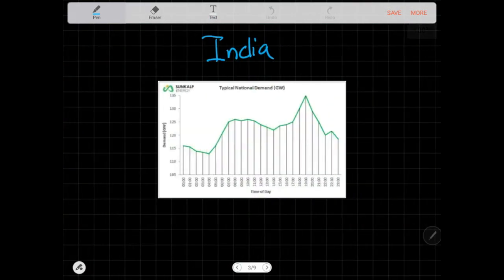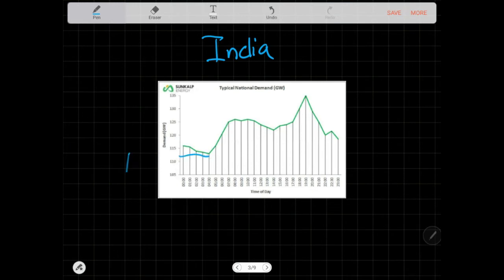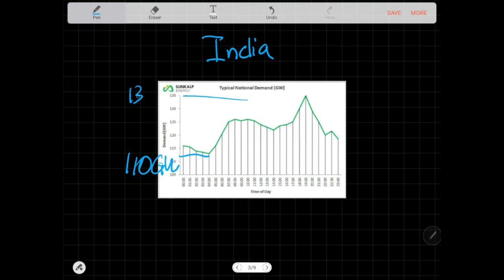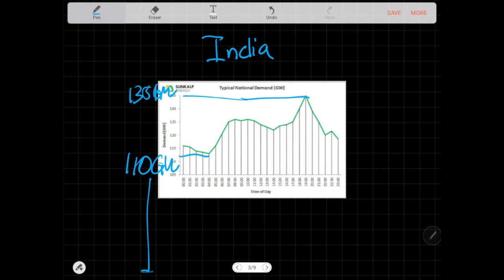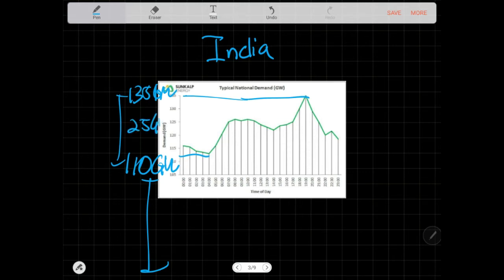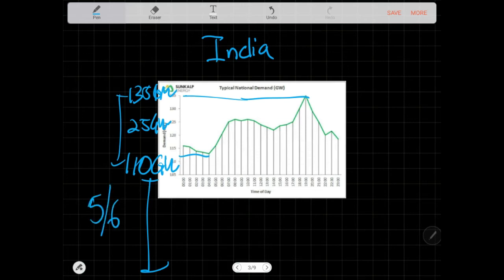We look into another country, let's say India. The lowest is around let's just say 110 gigawatts, and the highest is 135 gigawatts. So India is very industrial in energy consumption. Its minimum is 110 out of 135, so its expandable range is only about 25 gigawatts. Its baseload is a very large amount, like five-sixths of the time. Only one-sixth of the time it is expandable.